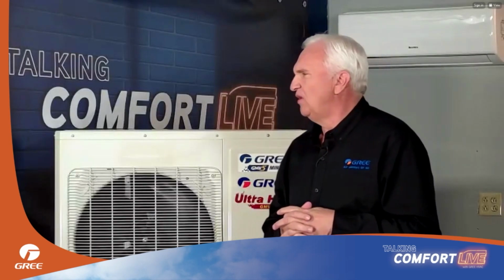That's a great question, Duane. Thanks. Yeah, so you can do up to 16 indoor units. They'll be wired in a daisy chain format, just like you would do for the communication wiring for the entire system. And lastly, you've got to make sure they follow the instructions for that particular controller, because they do need to go in and set the controller and tell it that it's controlling more than one indoor unit and how many it's controlling. They come factory set 1-to-1.